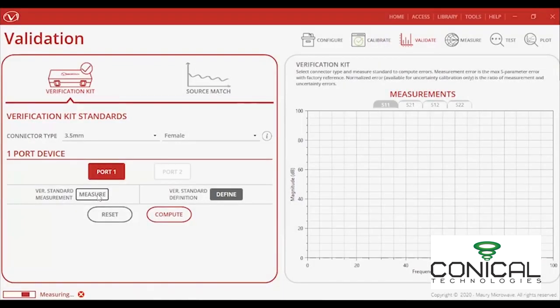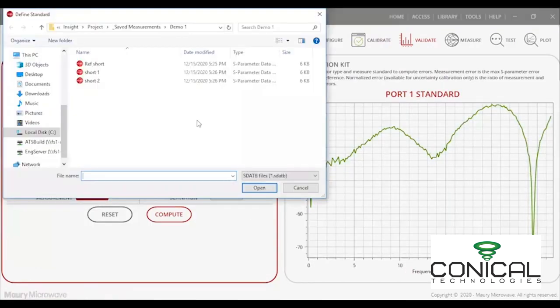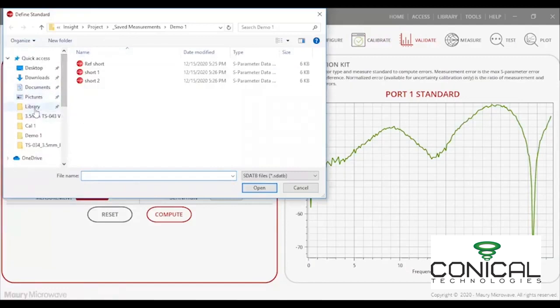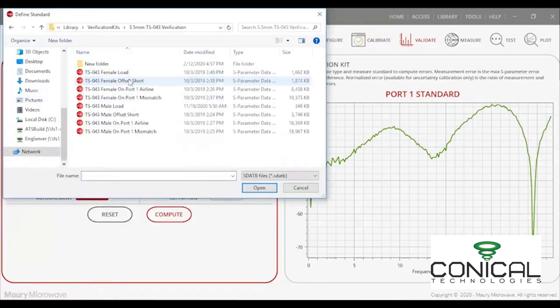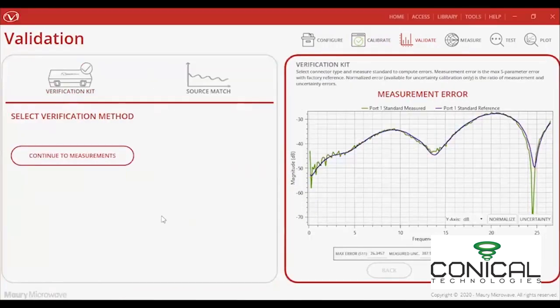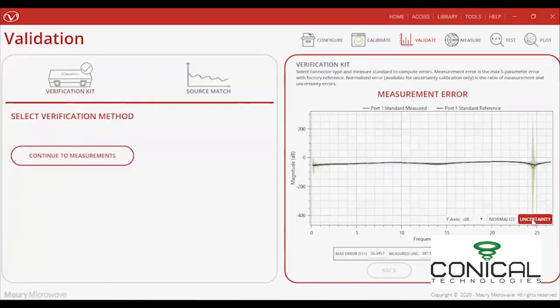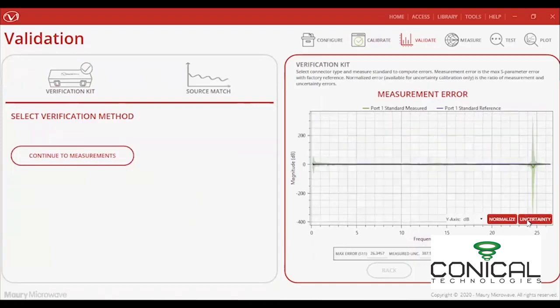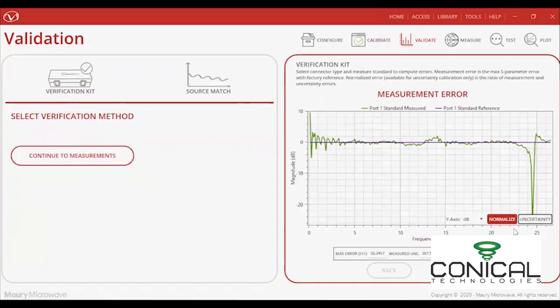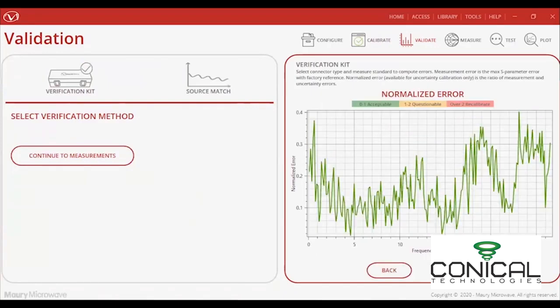Under this section, I can verify my calibration either using a 1 or 2 port verification standard, choosing between the load or short for the 1 port verification to the match or mismatch beaded airlines for the 2 port verification. I ended up choosing to go with the 1 port verification load. I then measured and fetched the definition file of the load standard so that the data can be computed to show the measurement error in my calibration.